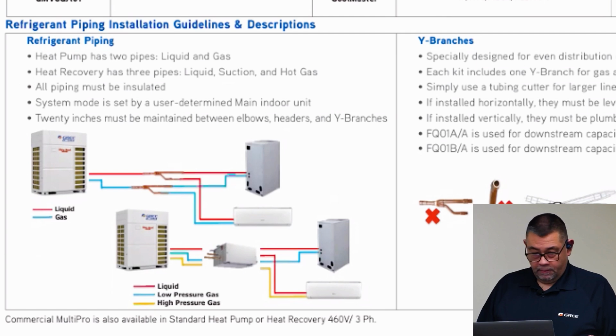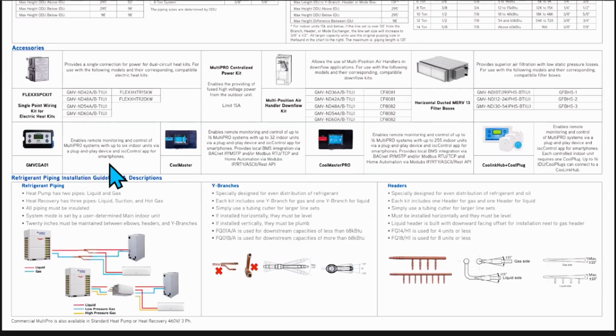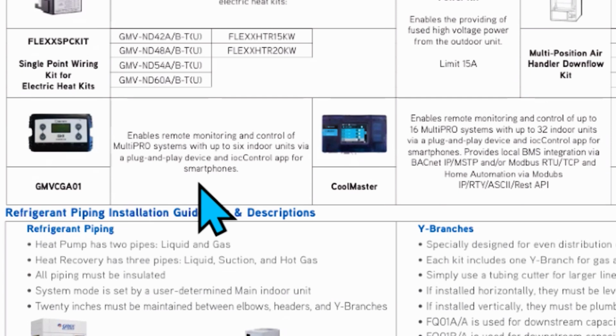We skipped over Cool Master, so let's go back to that for a minute. That Cool Master he's pointing to is a special build we had Cool Master do for us. It handles up to 6 indoor units, and can be across multiple condensers, but you can't exceed 6 indoor units. This hooks up just like central control. With Cool Master, we can now do 16 systems and up to 32 indoor units. If you have a bigger job than that, you can do Cool Master Pro, which handles 16 systems and up to 255 indoor units.